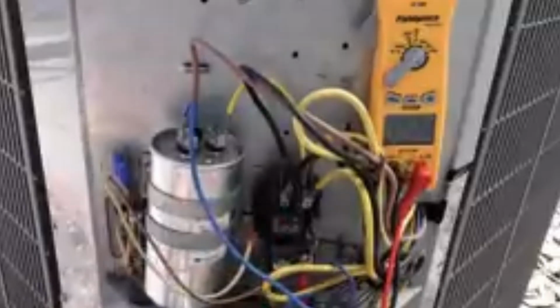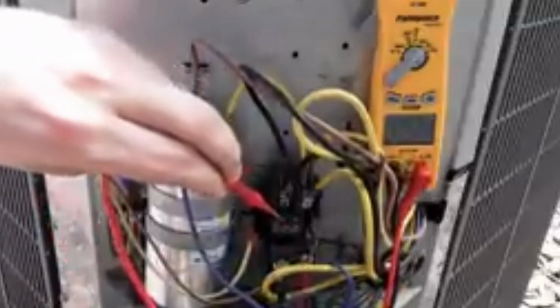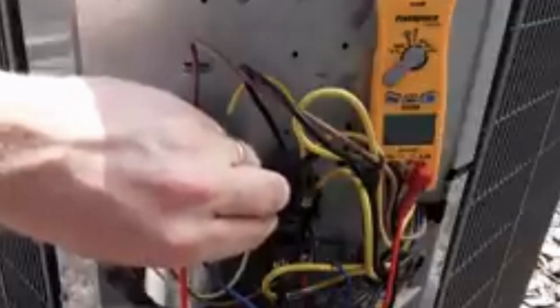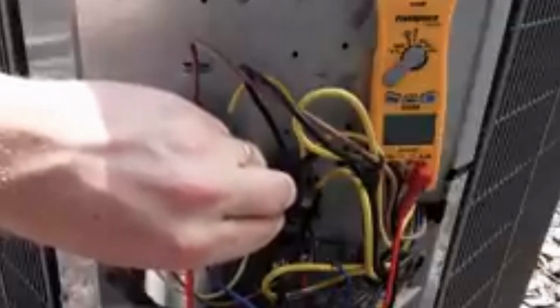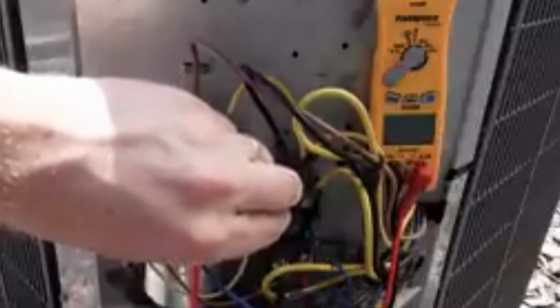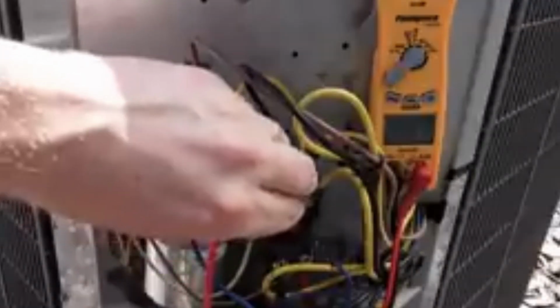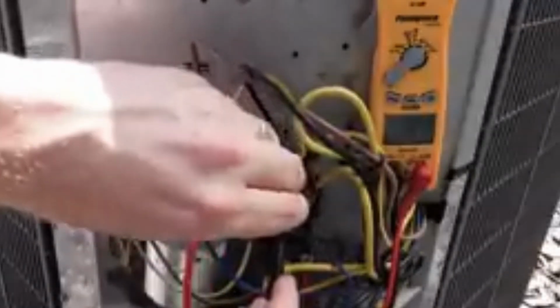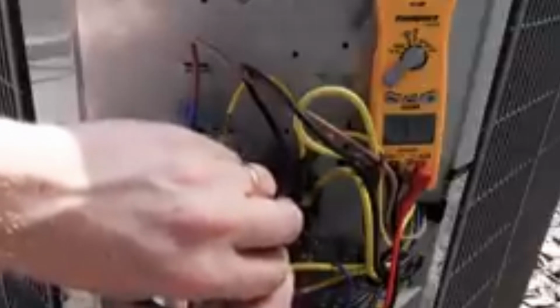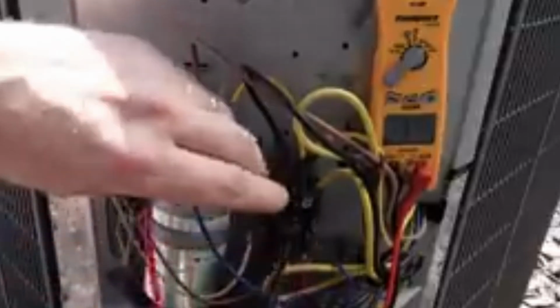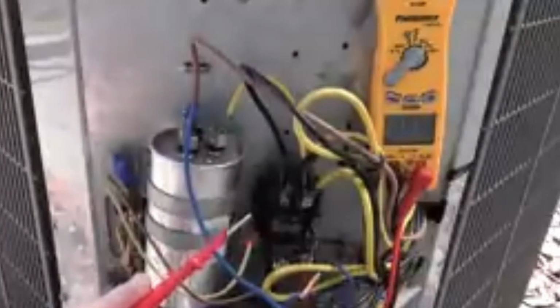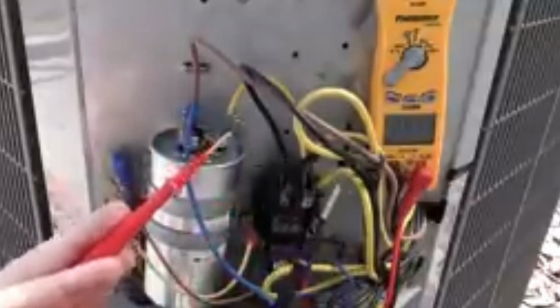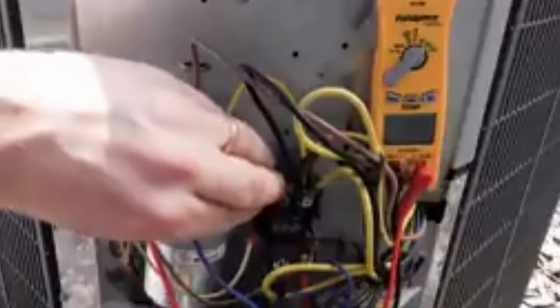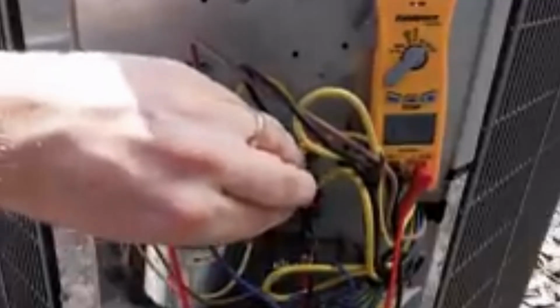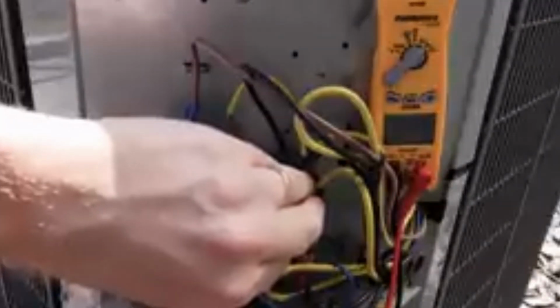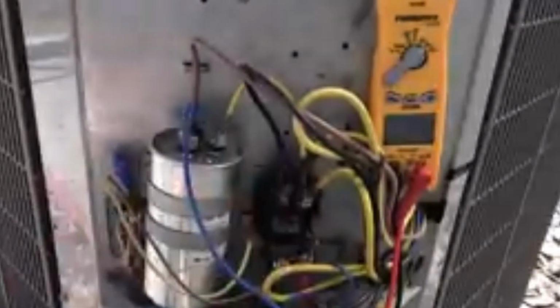A common mistake that technicians make is they attempt to measure across a switch. The voltage that's shown here of 0.3 volts is the voltage drop across the switch, and it's too small to even be accurately measured. It would be the same as taking our 2 meter leads and putting them in exactly the same position on the contactor. There's no potential difference between these 2 points, so I'm not going to get a measurement between them when I measure across the switch or at the same point. We'll do the same thing here and show you. It would only show a reading if we had a significant voltage drop.